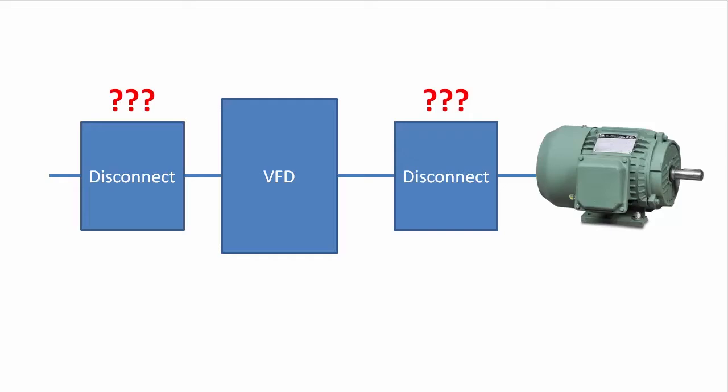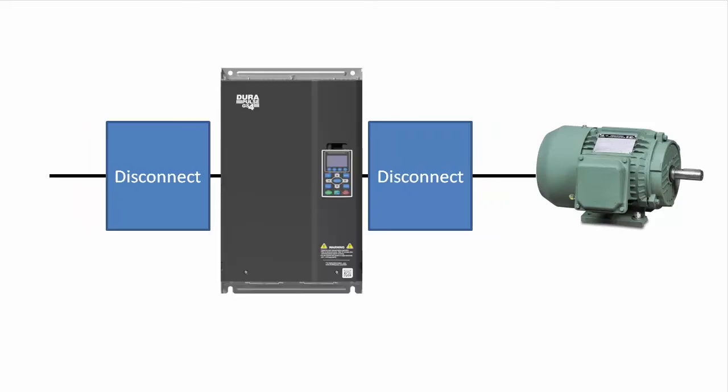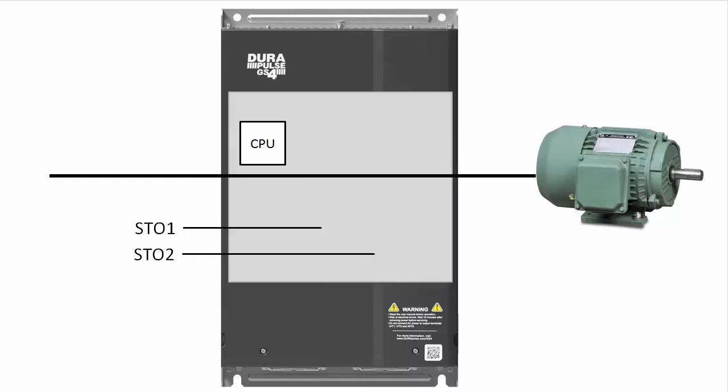The good news is you don't have to worry about any of that with the GS4 drive, because safe torque off is built into the drive.